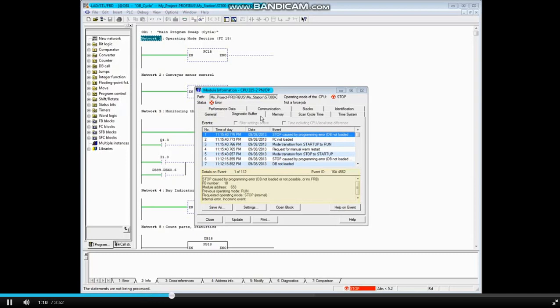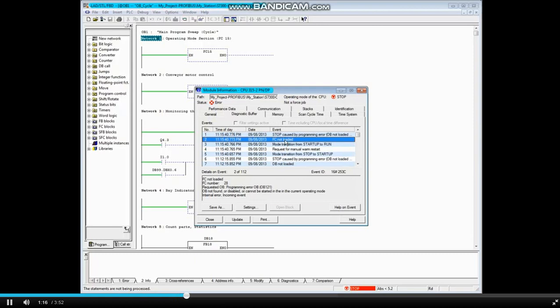Message 2 says that an FC was not loaded. Click on Message 2. The details of Message 2 show that it was Function 28 that was not loaded. OB-121 was called for when the fault occurred.